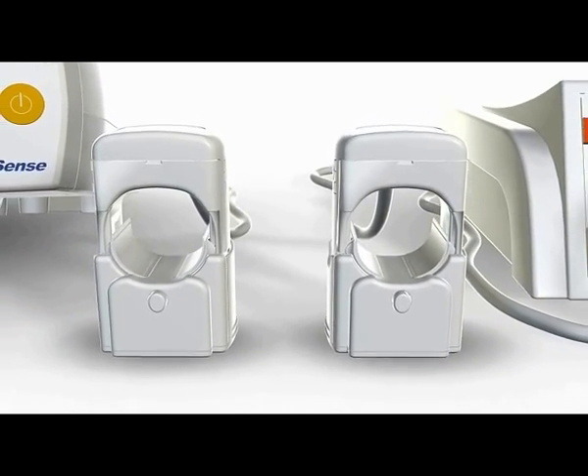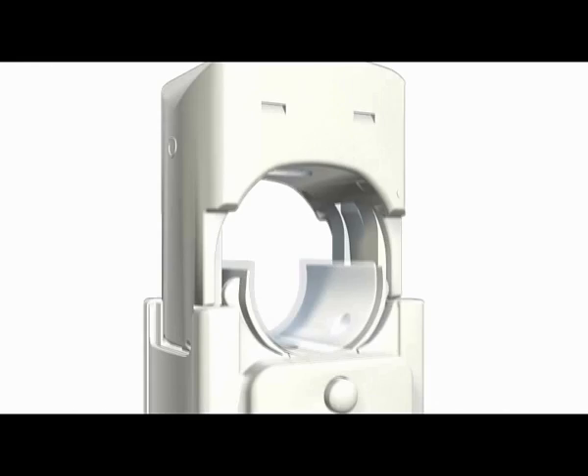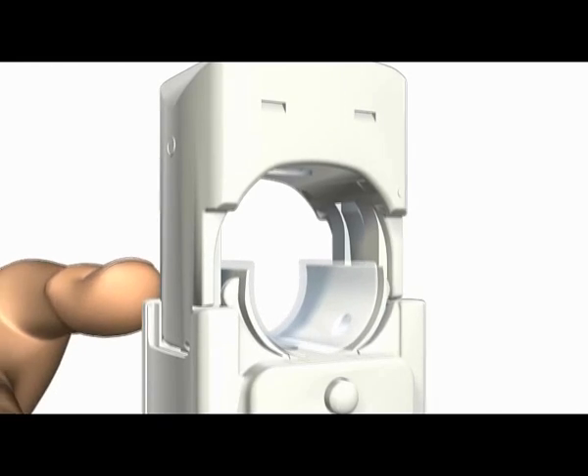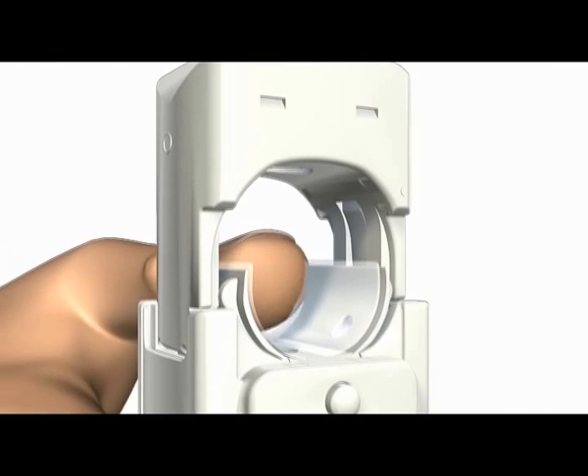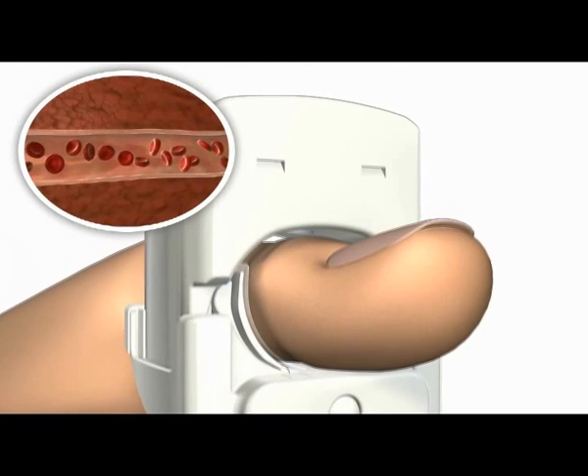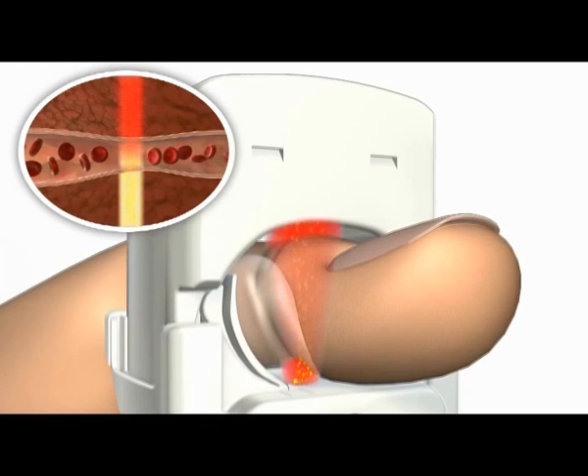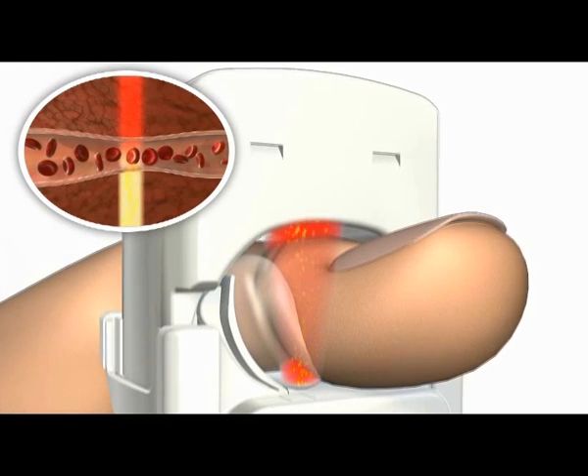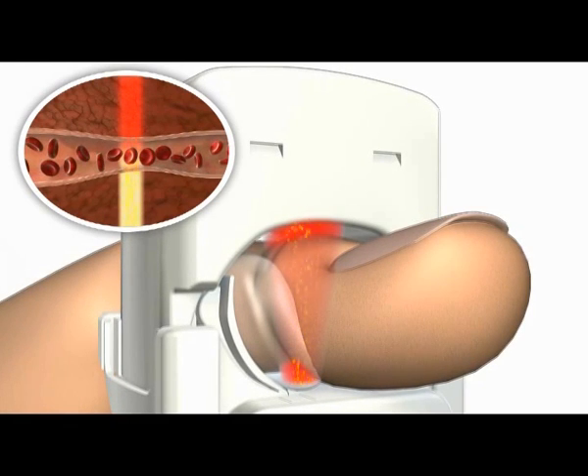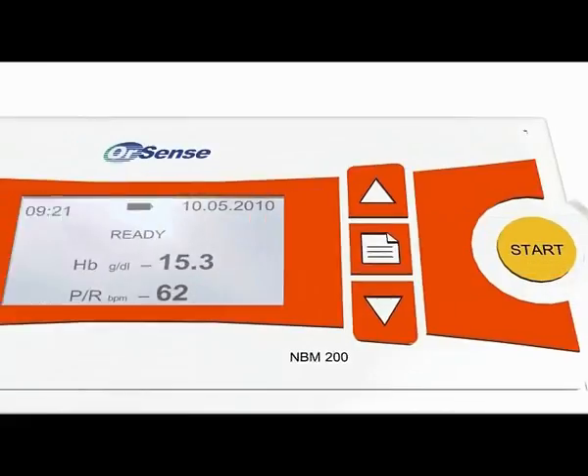The NBM200 and the NBM200MP devices include a reusable ring-shaped cuff and a corresponding monitor. The pressure applied by the cuff temporarily occludes the blood flow in the finger. A highly sensitive optical signal emitted from an array of calibrated light sources accurately measures light absorption and scattering.